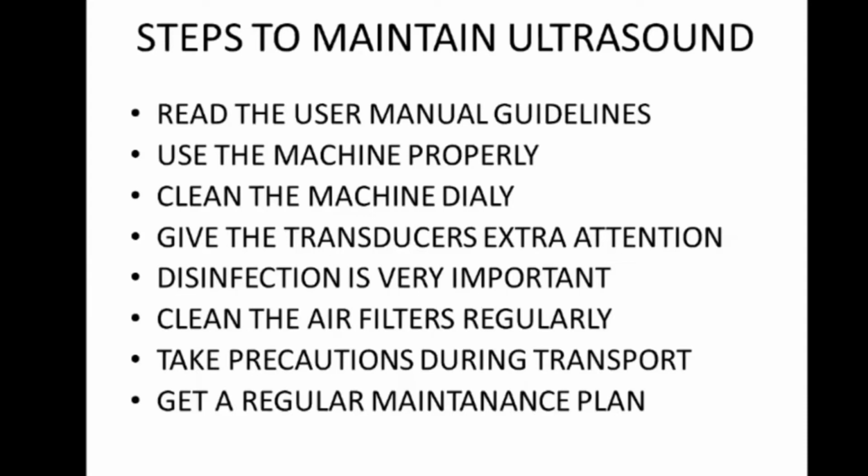If you fail to do that, the first thing that gets affected in the ultrasound is the monitor. The entire monitor gets collapsed. If you switch on the system, it won't turn on. Sometimes we have faced those issues when we are giving demos and all. So you should take precautions whenever you are transporting the machines.